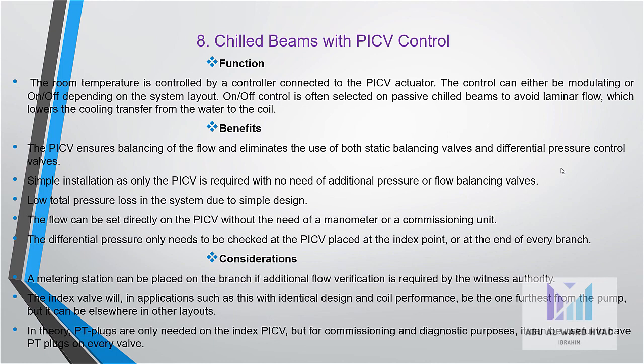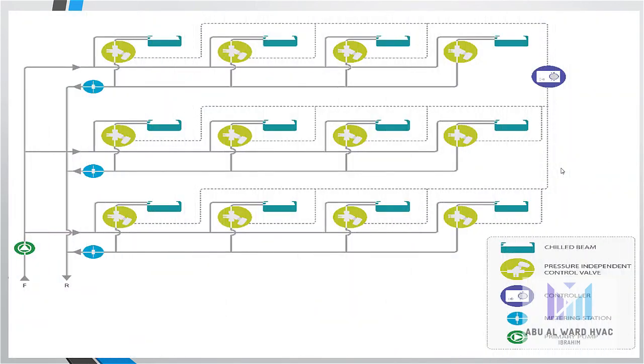Considerations: a metering station can be placed on the branch if additional flow verification is required by the witnessing authority. The index valve will, in applications such as this with identical design and coil performance, be the one furthest from the pump, but it can be elsewhere in other layouts. In theory, PT plugs are only needed on the index PICV, but for commissioning and diagnostic purposes it can be useful to have PT plugs in every valve. And here is the schematic for this.